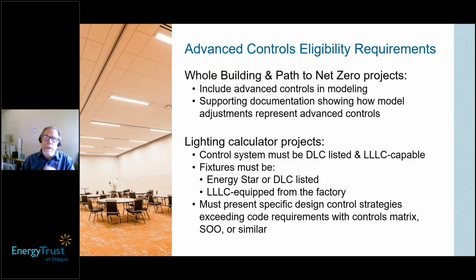If you install these advanced systems and don't tell them to trim down that time-to-off requirement, or tell the system to use those expanded daylight zones, then you won't make any savings over a code-compliant system, even with the advanced control system in there. So we want to see those strategies actually being implemented in the design, and it's good for us to have that early in the project so we know what you're planning.